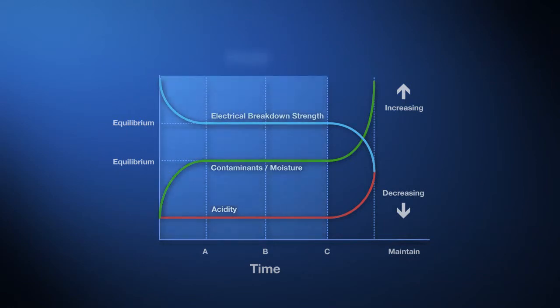In the vast majority of cases, we get a pass, and that's telling us there's no significant degradation of the oil, and therefore we can extend that maintenance period and retest the oil in five years.